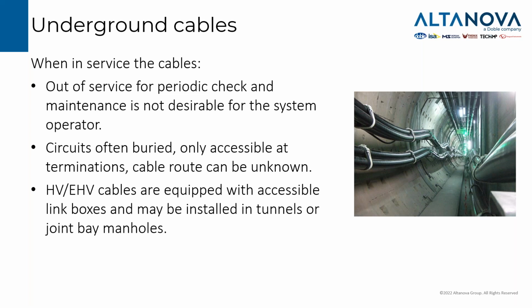The second problem is that such circuits are normally buried, so we don't have access points to the cable. And in many cases, especially in medium voltage, the cable route can be unknown. Instead, in high voltage and extra high voltage cable, we have few access points to perform some testing. Those are the link boxes and the terminations. Or in some cases, we can have the cables installed in tunnels or the joint bays organized in manholes. So we have a few more opportunities to check the health of the asset.